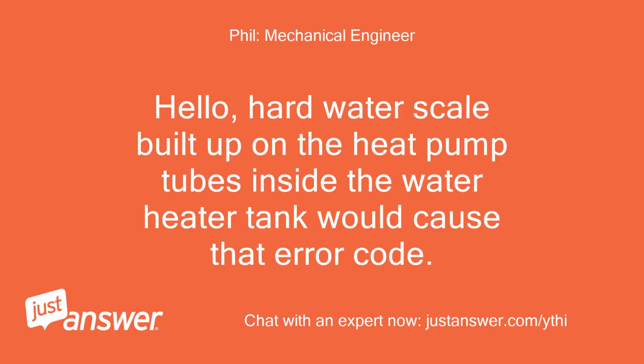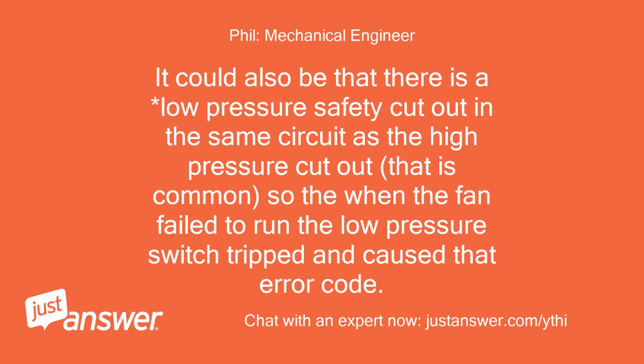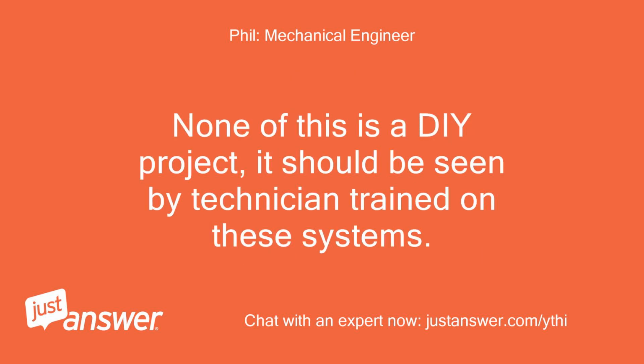Hello. Hard water scale built up on the heat pump tubes inside the water heater tank would cause that error code. It could also be that there is a low pressure safety cutout in the same circuit as the high pressure cutout. That is common, so that when the fan failed to run, the low pressure switch tripped and caused that error code. None of this is a DIY project. It should be seen by technician trained on these systems.